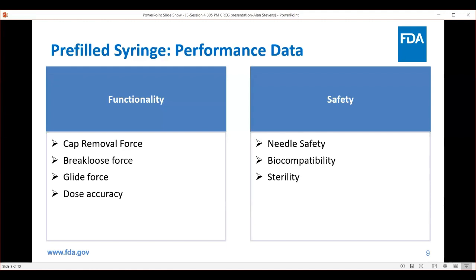Biocompatibility and sterility are important. Generally, these would be covered as part of the CMC review, and so CDRH is generally not going to be specifically looking at those data for a prefilled syringe. Certainly for a co-packaged empty syringe, we would be assessing those criteria. And for needle safety, I skimmed past this, but earlier when I listed the standards, the ISO 23908 standard is the method that we use for assessing needle safety.